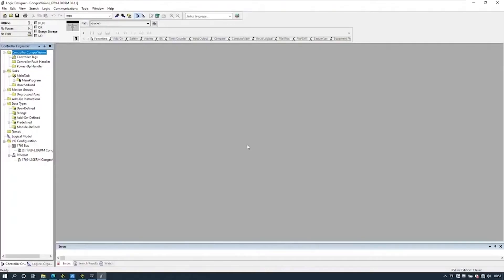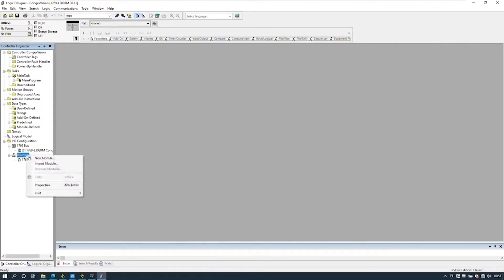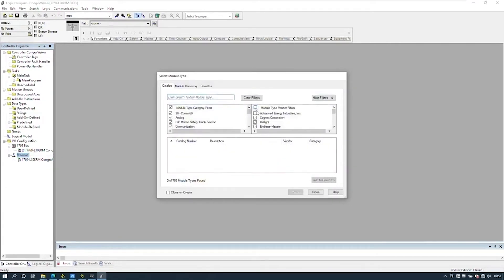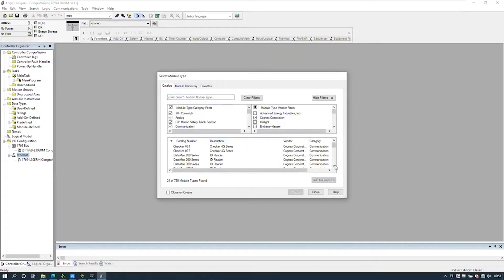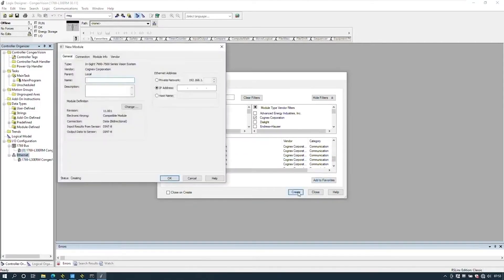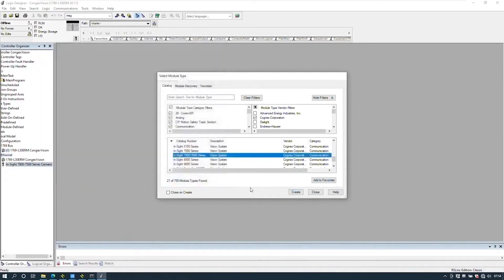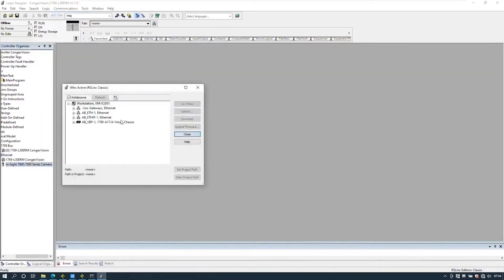Now open up the Logix Designer or RSLogix 5000 software and a program. To add the Cognex camera, right mouse click on the Ethernet port and select New Module. Select Cognex in the vendor filter and find the correct part number. Press the Create button and the new module dialog box appears. Give it a name and use the IP address allocated to the camera. You can change the data structure and revision if needed, but we'll leave it as default. Now download to the PLC.